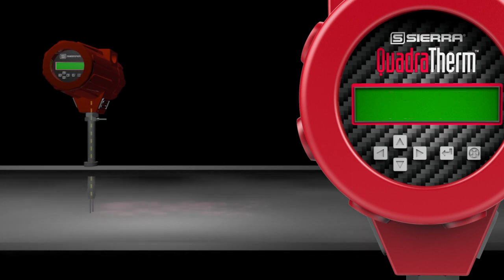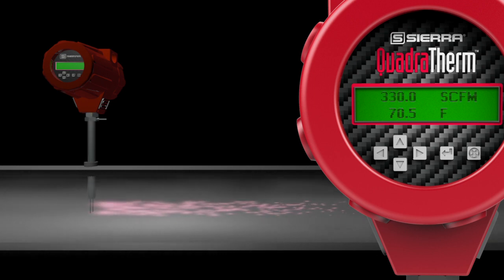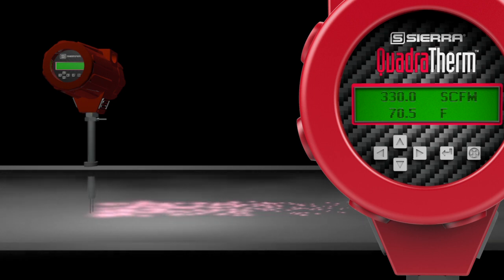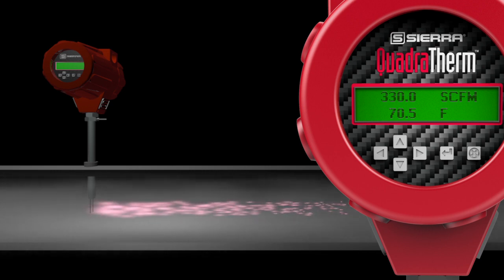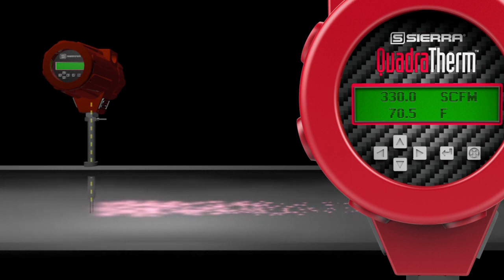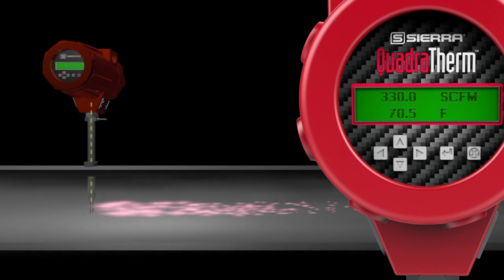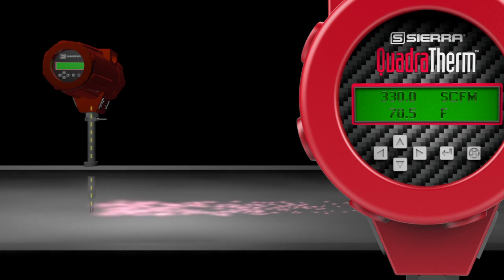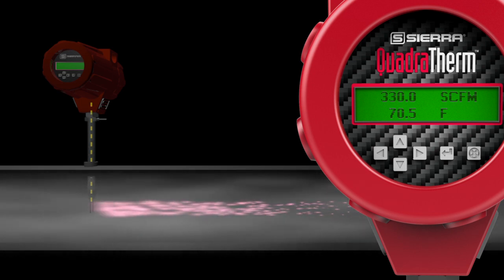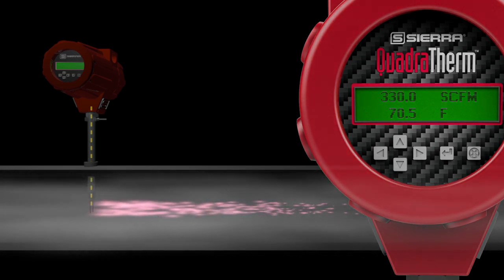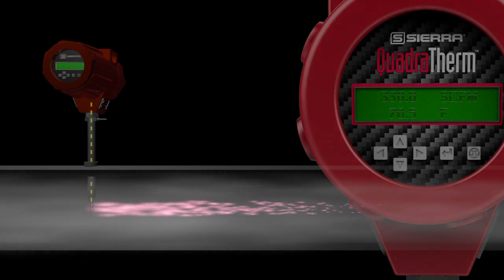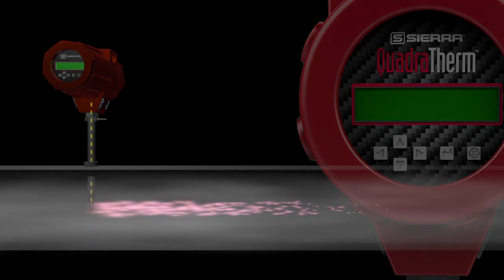Now, let's increase the gas mass flow velocity 10 times to 330 standard cubic feet per minute. You can see much more heat dispersion, the meter immediately reads a higher flow rate, and much more electrical power is sent to the velocity sensor to maintain the constant temperature differential required.